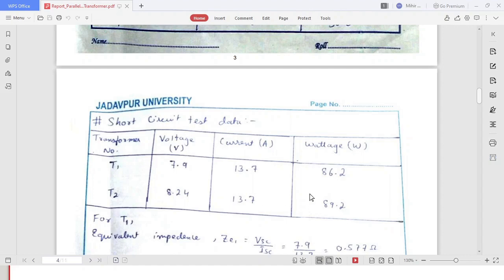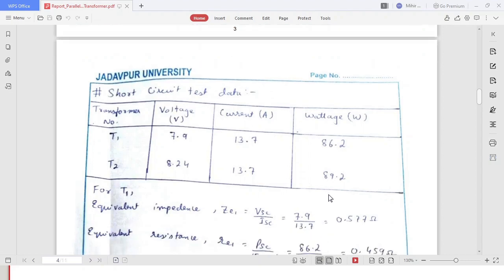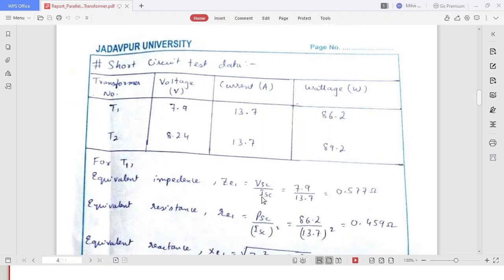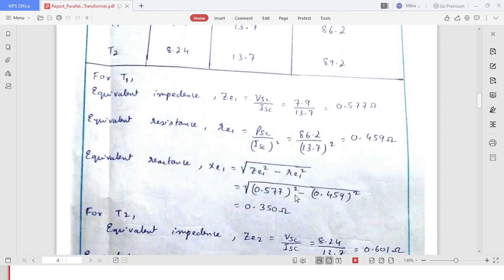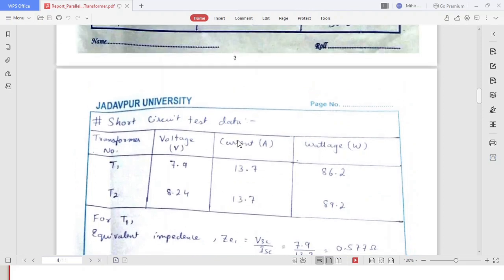For transformer 2 also 13.7, but their voltages are different: 7.9, 8.24. Here wattage 86.2, 89.2. From this data you can calculate the impedance of the transformers. Here ZE1 is VSC by ISC, and as this wattage is given, from there you can calculate the resistance of the winding. From this one, you can calculate the reactance of the winding. Once you know this impedance value, you can calculate the current sharing of the transformers.